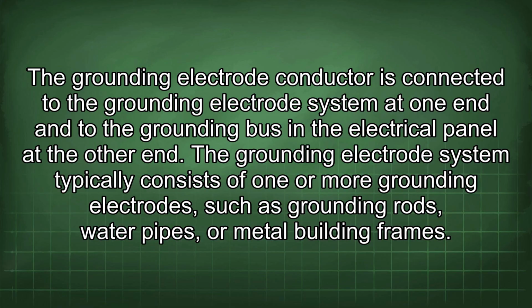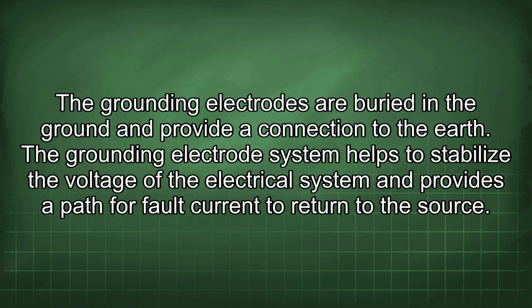The grounding electrode system typically consists of one or more grounding electrodes, such as grounding rods, water pipes, or metal building frames. The grounding electrodes are buried in the ground and provide a connection to the earth. The grounding electrode system helps to stabilize the voltage of the electrical system and provides a path for fault current to return to the source.